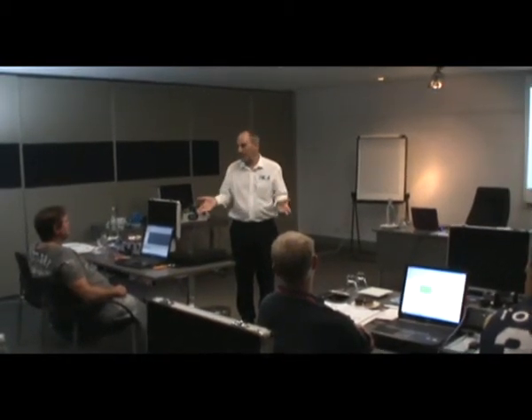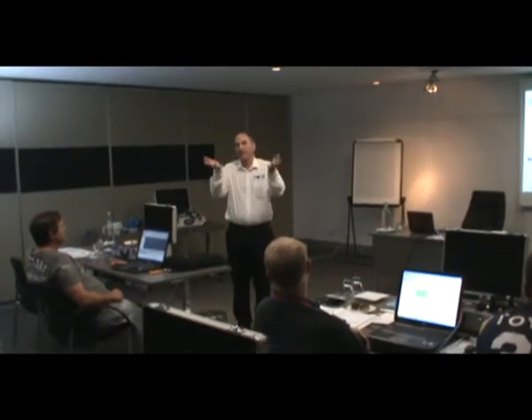Of course, as soon as they fall off the bus, the watchdog timers trip out and they fail safe. The outputs get switched off, which means that the current goes back down to 4.5 amps and the 24 volts comes back up again. Everybody's happy. So the symptom is that several devices have fallen off the bus because the current momentarily went over the limit. But when you look at this without knowing what the cause is, it looks like a PROFIBUS failure.